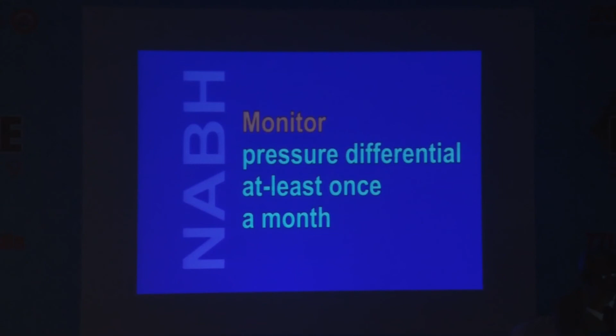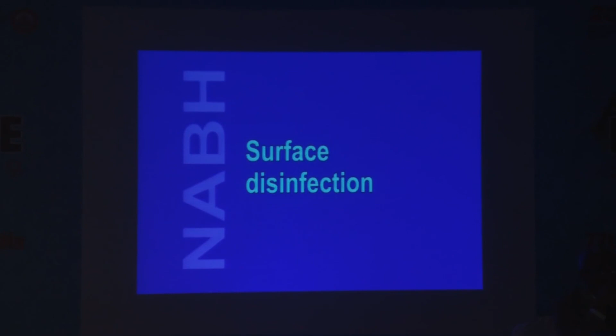Environmental processes, certain things they want to monitor, like humidity and temperature. That is mainly for central AC when you have the air handling unit. Pressure difference you can get only in central unit. At least once a month it has to be monitored. And for surveillance by the microbial open plate method, they will want to see records. And surface disinfection should be carried out as advised. These are the things where they mainly insist.